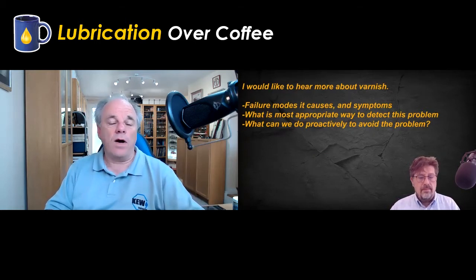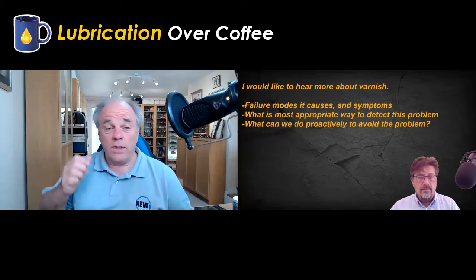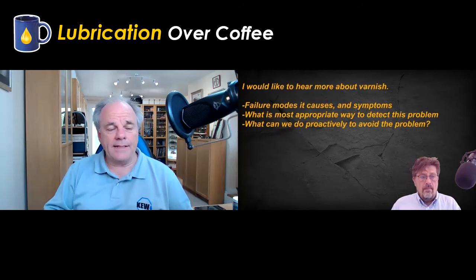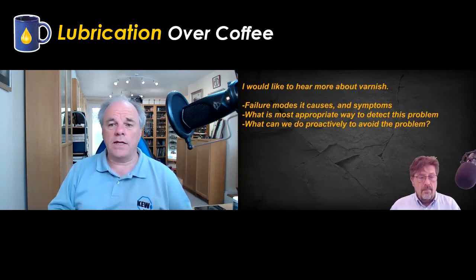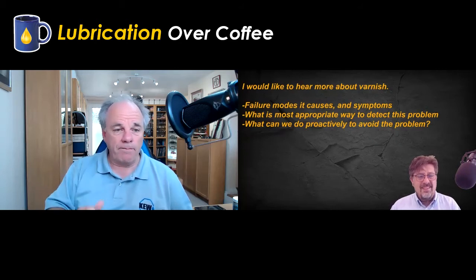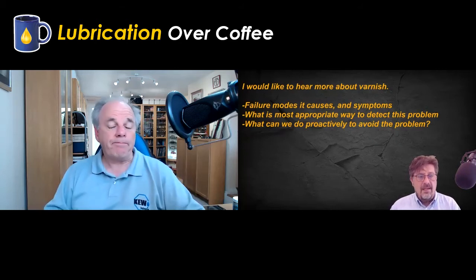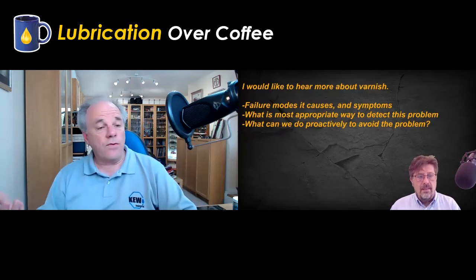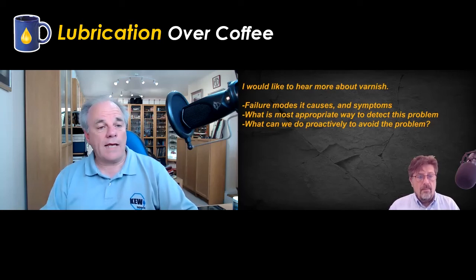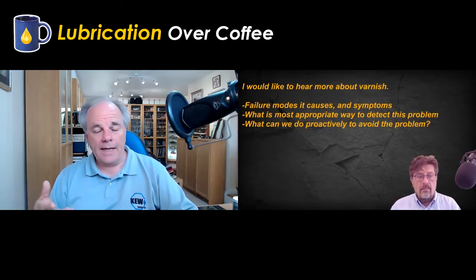If we consider thermal decomposition and oxidation of the oil — oxidation being the WHAM effect, where WHAM stands for Water, Heat, Air, and Metals — the heat aspect and thermal decomposition will be much more prevalent in territories with higher ambient temperatures. The Middle East region sees a lot of this problem, and also assets like gas turbines, where you have extreme temperatures in the bearing housings.